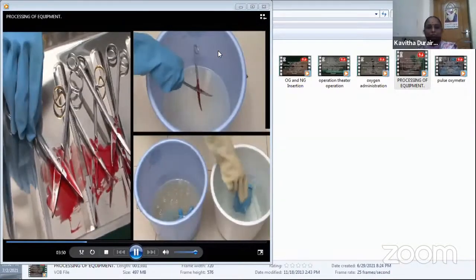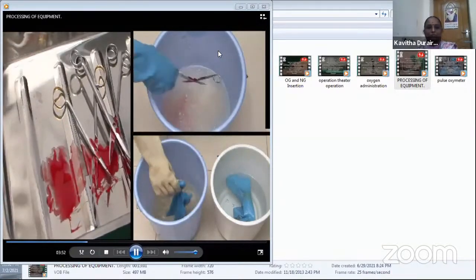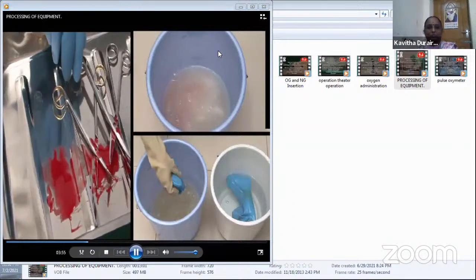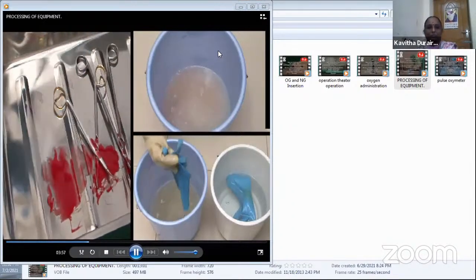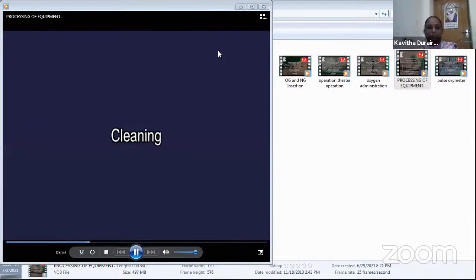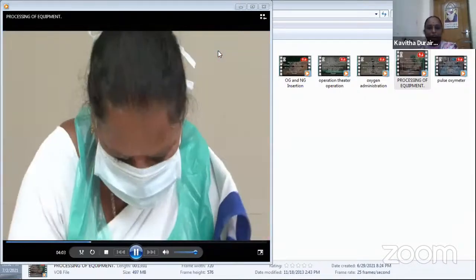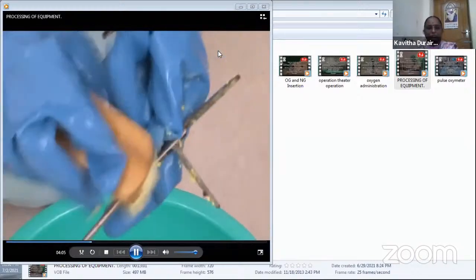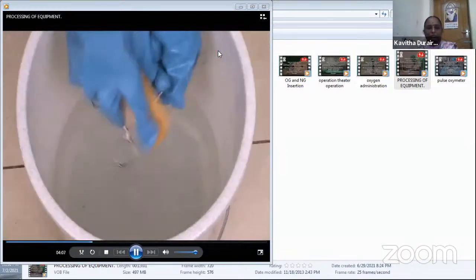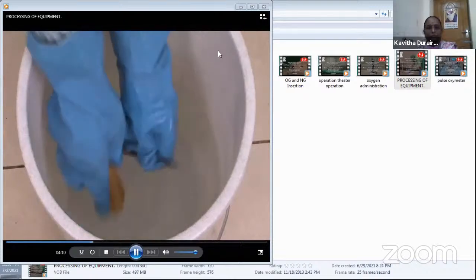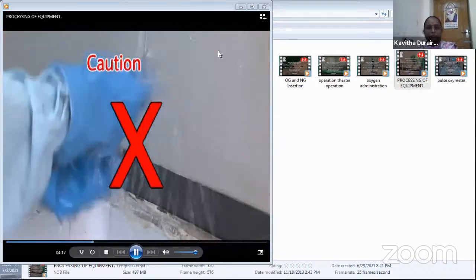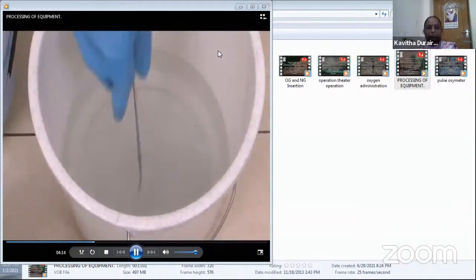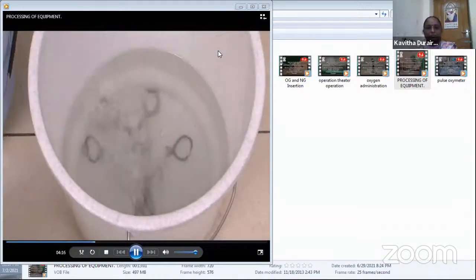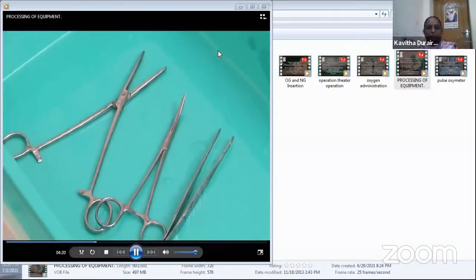This process is called decontamination, which makes the used items safe for further processing. Cleaning. She scrubs the instrument using a brush and a detergent. Scrub the instruments in a container filled with water to avoid splashing. Rinse them thoroughly in another bucket of fresh water to remove all detergent, and then air dry.